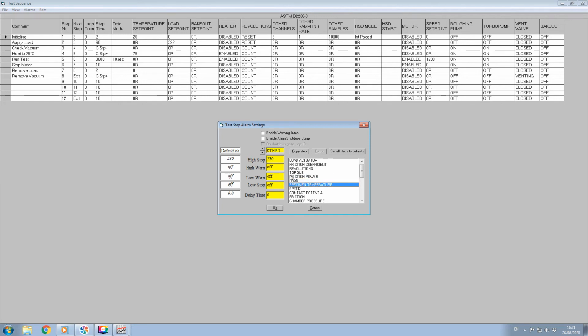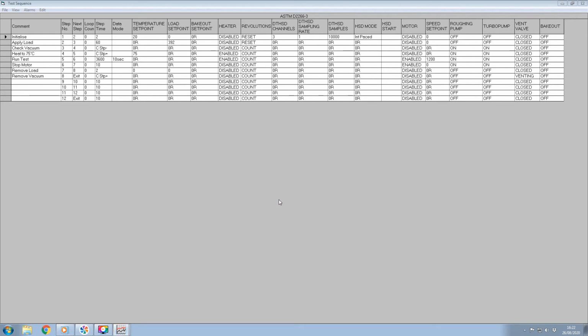Alarms may be set for each step in the test and for each required parameter, although it is usually only necessary to set alarms on the most important parameters, for example, load, temperature and friction. Use the up and down arrows next to the step number box to pick each step. Then set the alarm levels for the required channel from the list on the right. The alarm levels may be copied from one step to another using the Copy Step and Paste buttons. When an alarm is triggered, a message will appear above the control panel and the event will be recorded in the data file. A shutdown alarm will terminate the test.